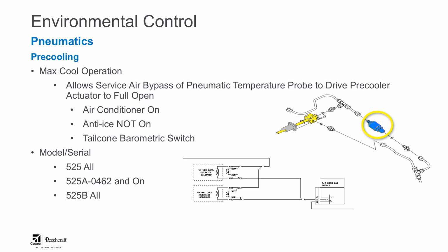One is that the air conditioner is commanded on. If the air conditioner is turned on, that means we're trying to cool everything down in the cabin as much as possible. We want to add extra cooling through the pre-cooler, and what happens is with that air conditioner command, that solenoid valve opens up and allows 23 psi to bypass the pneumatic temperature probe and go straight to the modulating valve, which will then drive it to the full cold position or full cooling position, max cool.